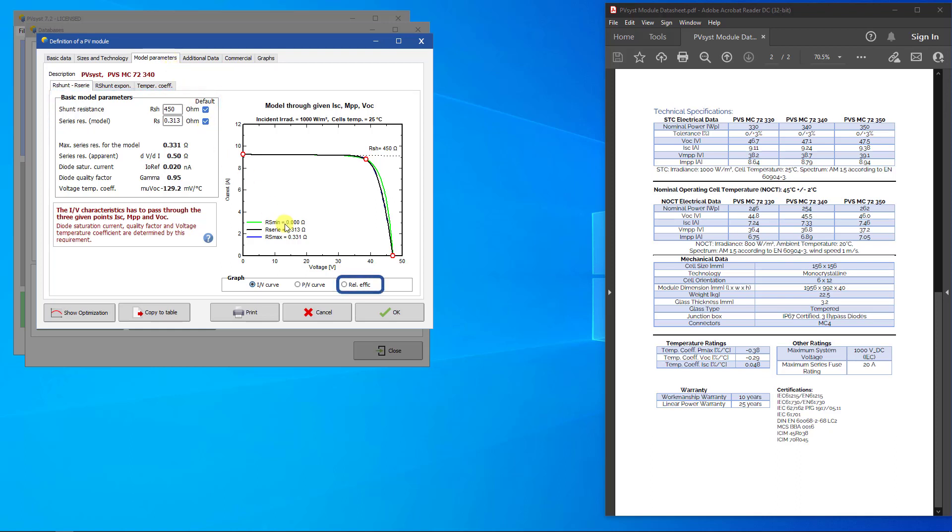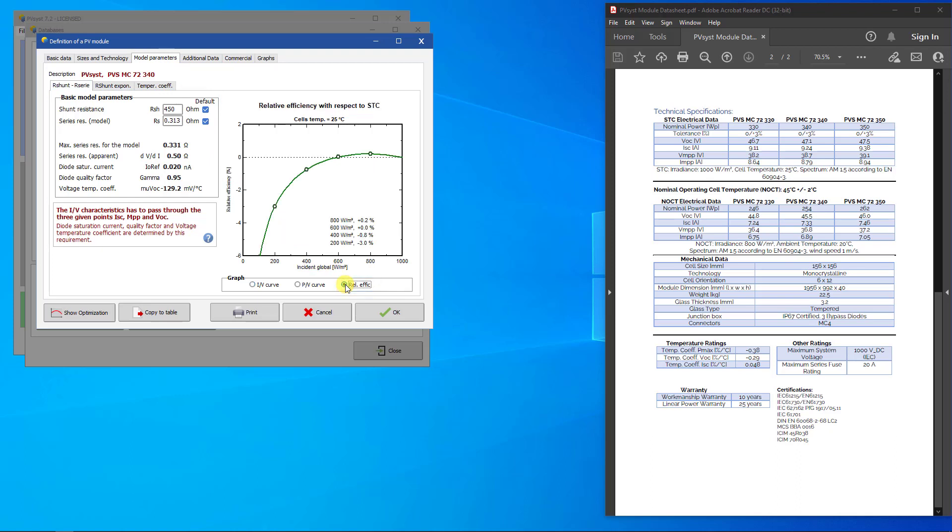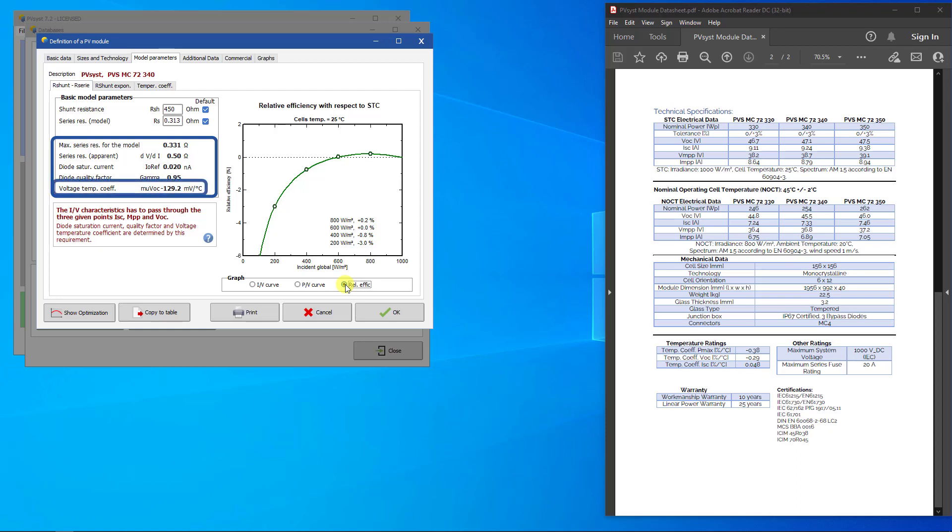Click on the radio button for relative efficiency. The Rshunt value mainly determines the low light performance of the PV module. The default value set by PVSYST for crystalline silicon is negative 3% at an irradiance of 200 watts per square meter. If this value is not reachable, the value for R shunt should be increased. In the lower part, you find specific parameters determined by the model. Here the muVoc temperature coefficient is a result of the model. It will not necessarily match the value on the datasheet.